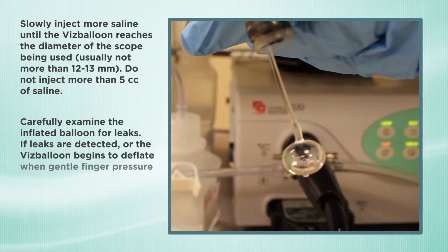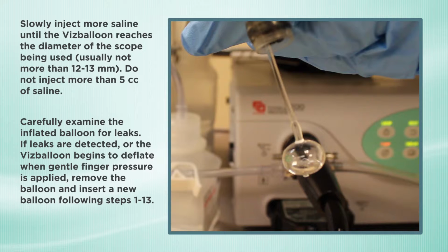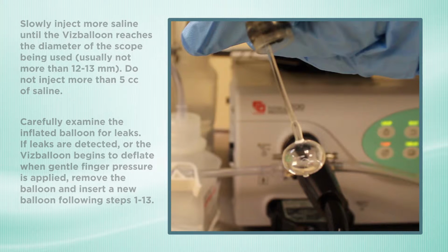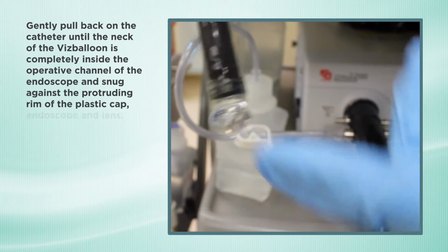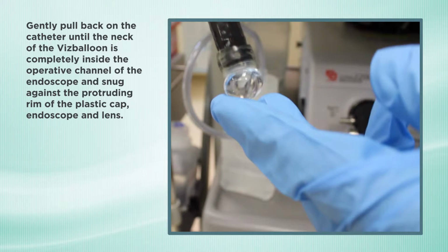Carefully examine the inflated balloon for leaks. If leaks are detected, or the Vizballoon begins to deflate when gentle finger pressure is applied, remove the balloon and insert a new balloon following steps 1 through 13. Gently pull back on the catheter until the neck of the Vizballoon is completely inside the operative channel of the endoscope and snug against the protruding rim of the plastic cap, endoscope, and lens.